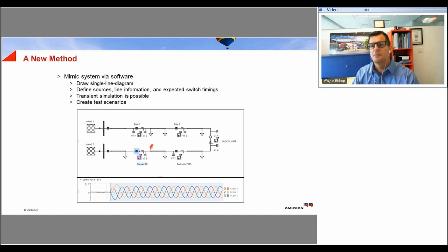If a breaker or recloser's opening and closing times are known, or have been previously measured using any kind of breaker timing device, the software can allow for the input of these times, which are taken into consideration to ensure the most realistic kind of test. Any modern secondary injection test set typically has built-in circuit breaker simulations, which can be extremely beneficial for this type of testing. And using any kind of binary output on these test devices, 52A or 52B contacts can also be simulated. It does not require the circuit breaker or the recloser to be connected during such a test.